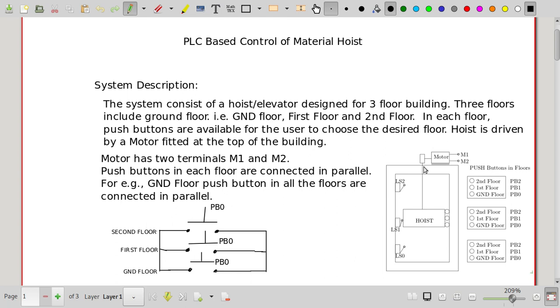In each floor — ground floor, first floor, and second floor — three push buttons are available. These buttons are connected in parallel. For example, all the ground floor push buttons across all floors are connected in parallel, so if any one push button is pressed, that particular input will be energized. Through this parallel connection of three sets of three buttons, the number of PLC inputs is reduced to just three.